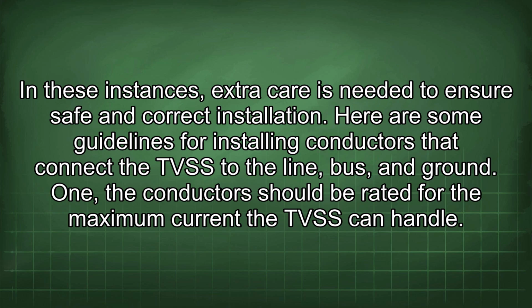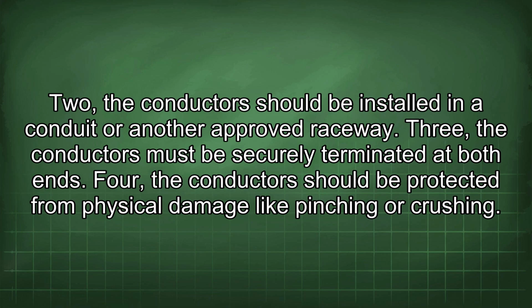Here are some guidelines for installing conductors that connect the TVSS to the line, bus, and ground. 1. The conductors should be rated for the maximum current the TVSS can handle. 2. The conductors should be installed in a conduit or another approved raceway. 3. The conductors must be securely terminated at both ends. 4. The conductors should be protected from physical damage like pinching or crushing.